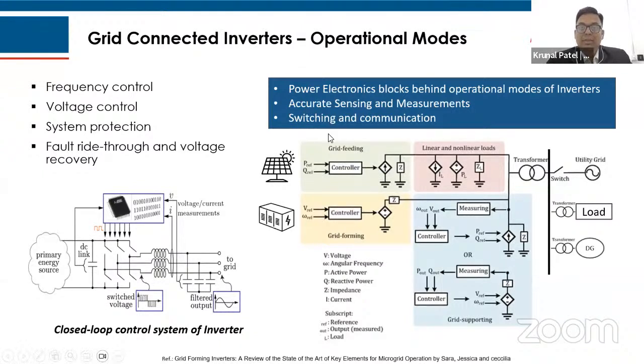Going further into the block diagram, I would like to highlight that if the PV inverter is connected in a microgrid scenario, it is connected as a grid-feeding inverter, transmitting active and reactive power to the grid. In case any battery system is connected to the microgrid, it is connected as a grid-forming inverter, where its main role is to maintain the voltage and frequency of the microgrid. With respect to these two characteristics, the PV inverter acts as a current source, whereas the battery PCS, which we call the PCS controller, is considered a voltage source of the inverter.